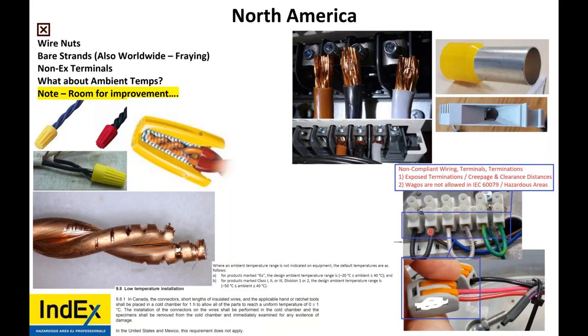Terminals, well, you can see all the copper on the strands. So reduce creepage and clearance distances. Now somebody might say, well, it meets the 6 millimeters. Over time, heating, hot, cold, contracting, it will move. It's not a good termination. We have the tools. We have the ferrules to do this.